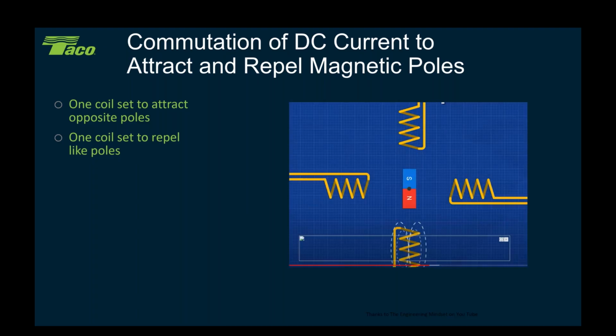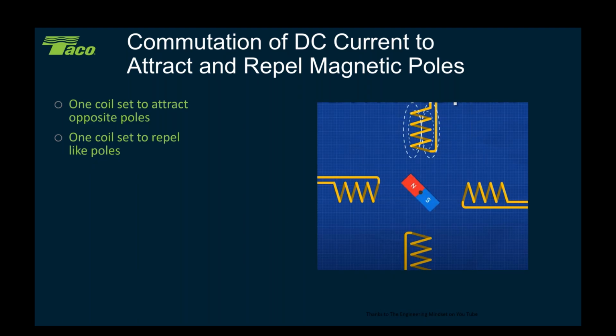So what happens is we go along, and as the field continues to rotate, we just cause the rotor to move. It's that simple. Okay, and as we go along, it just continues its merry way as we rotate around. And the difference is with ECM motors, we always know where that shaft is at. Okay, there's technology built in there. It gets into the IP of how we build the motors. But what we know is we know where that shaft is at any point in time. We know what position it's in from 0 to 360 degrees. So we know where it is all the time.